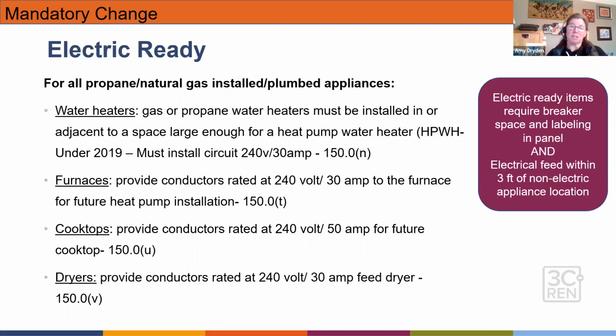The other piece of this is electric ready. So this was first introduced in our 2019, where we saw pre-wiring for heat pump water heaters. You may recall that introduction, where if you have a heat pump water heater you must pre-wire, or if you install a natural gas or propane water heater, you must pre-wire for a heat pump water heater. Well, under 2022, we're taking it a little bit farther. Now for water heaters, we still have that pre-wire in place for our 240 volt, 30 amp water heater, but there are also space requirements to ensure that there is enough physical space to install that heat pump water heater. We know heat pump water heaters are a little bit larger than our gas water heaters, and so we now have an additional space requirement.